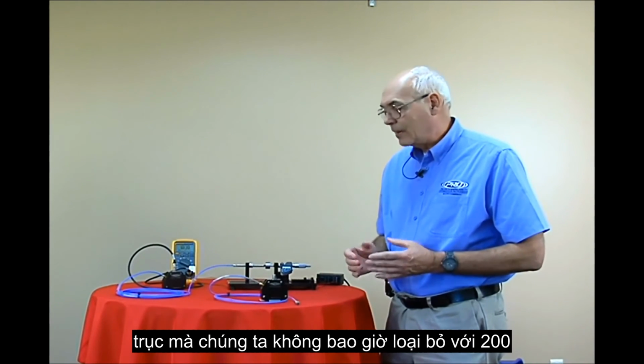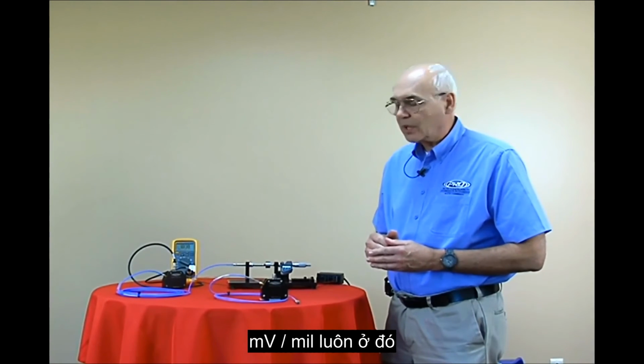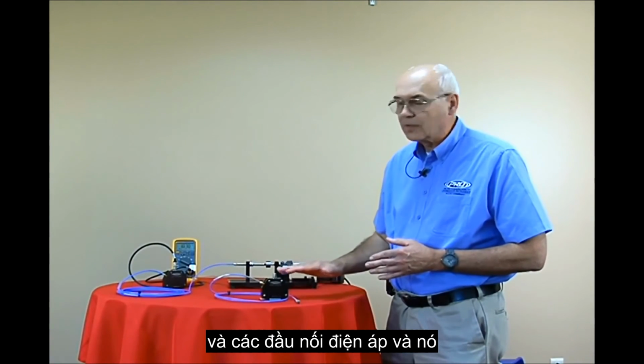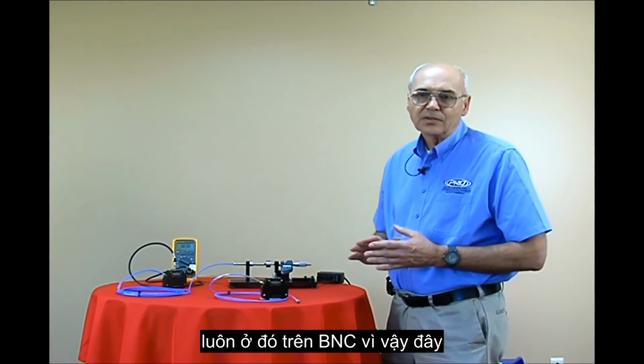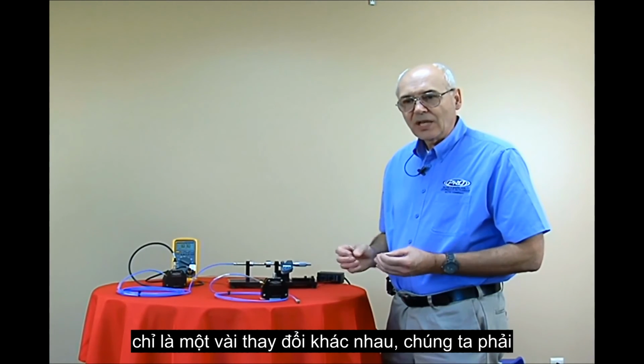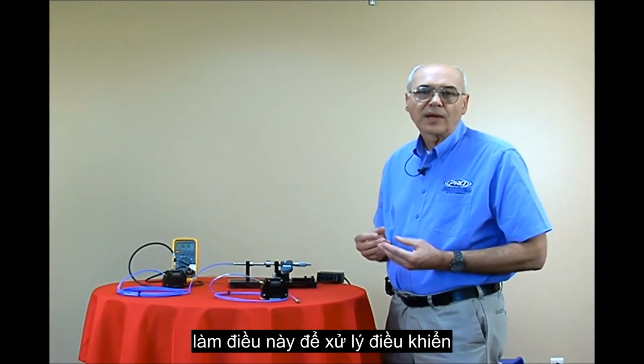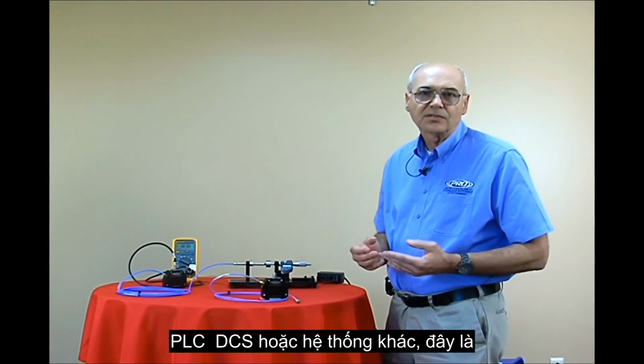We never do away with the 200 millivolts per mil — that's always there in the voltage terminals and always there on the BNC. These are just some different changes we've made to make this available to process control, PLC, DCS, or SCADA systems.